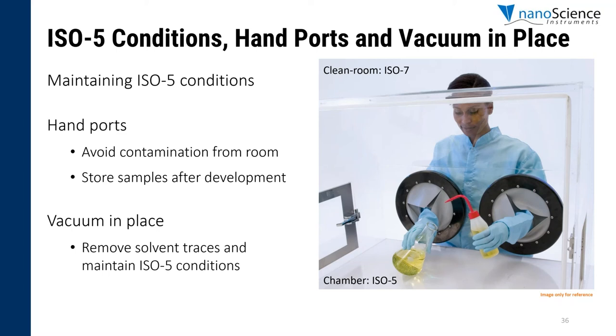Another aspect we offer is a vacuum in place. This is something a lot of people have been asking us about recently. When you're generating electrospun scaffold or electrospray particles, there's a chance of having residual solvent. If we implement this vacuum inside the chamber, we can remove any trace of solvent in the sample, either the fiber or the particle. This benefits the sample, as it will be free of solvent. You can package it in your packaging material and still retain ISO 5 conditions. This is really advanced and mainly used for tissue engineering or pharmacological applications, but it can be available for anyone interested.